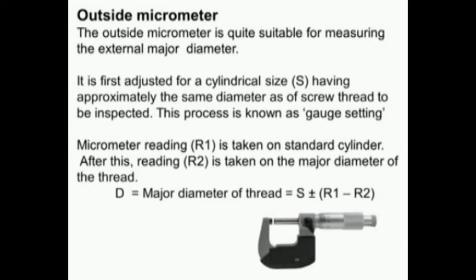Care should be taken to see that the crests of the thread are not over-pressurized. When we move the anvil, we should take care that as soon as the anvil just touches the crest of the thread, we should stop the rotation of the thimble. So again the procedure is the same. Reading is taken with the standard or setting cylinder.